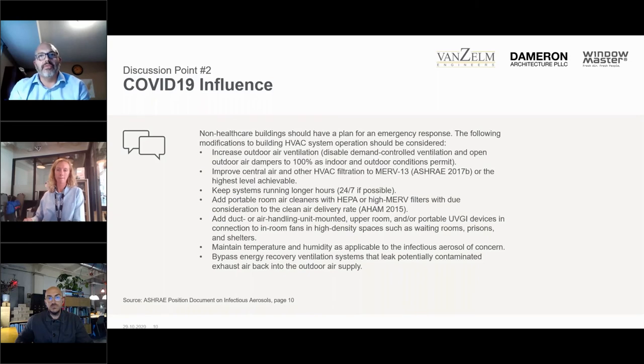Other ways to do filtration and ventilation control: they're talking about ultraviolet filters. That's an option too. It helps kill the virus. So in recirculating air systems, whatever particulates get captured in the filter, you can use UV light to disinfect them so that they wouldn't be transferred back into the space. Obviously, you want to do what you can to maintain proper temperature and humidity, depending on how long the virus can live. And the one thing that is in here, for instance, as the example given with the energy recovery wheel, is that it's transferring air from the return to the supply.